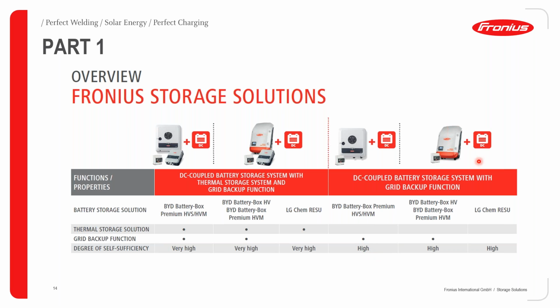Okay, moving on to the 4th solution, which is the Fronius Symo hybrid with a smart meter and with a DC battery. Okay, such a system is compatible with the BYD battery box HV or the BYD battery box premium HVM or even the LG Chem RESU. There is no thermal storage solution for the 4th system because we don't have an Ohmpilot installed, and we do offer a grid backup functionality only when the BYD is installed with the Symo hybrid. Degree of self-sufficiency again is very high. Well, not very high, but just high.